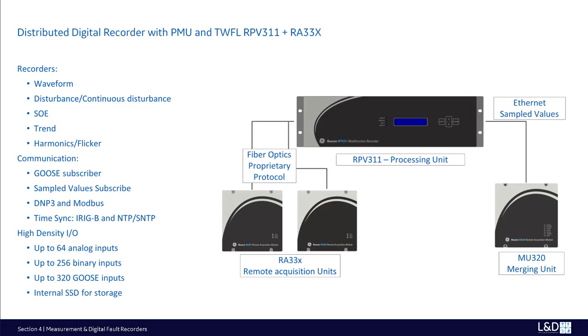The Reason RPV311 digital recorder with PMU and TWFL works as a distributed DFR, which needs remote acquisition units like RA33X. As a DFR, it can record waveform, disturbance, and continuous disturbance, SOE, and trend, same as the DR60. The RPV311 can also measure the flicker and harmonics for the power quality. For the communication, RPV311 is only the subscriber for Goose and sample values. It can transmit the data to SCADA via Modbus or DNP3 protocols. Like DR60, it can be time synchronized with IRIG-B and PTP.